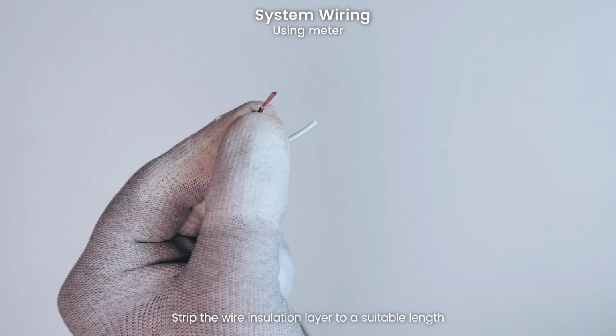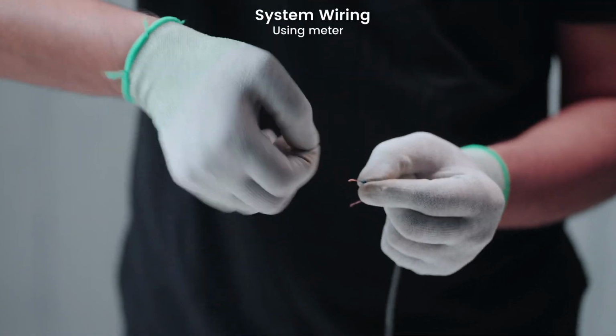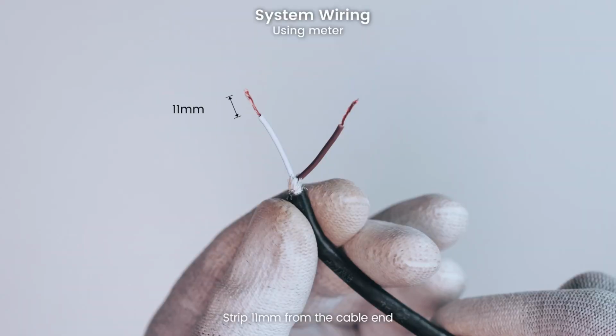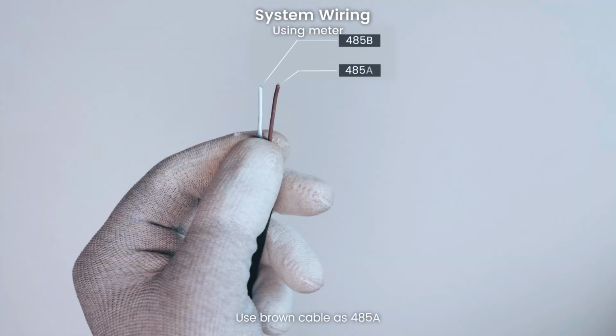Strip the wire insulation layer to a suitable length. Strip 11 mm from the cable end. Use brown cable as 485A, white cable as 485B.